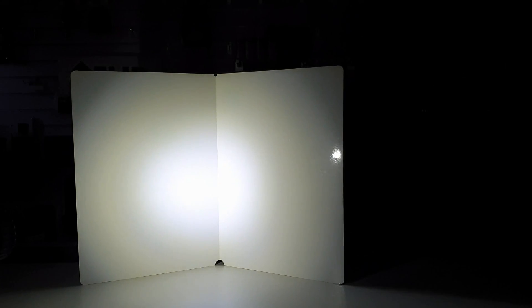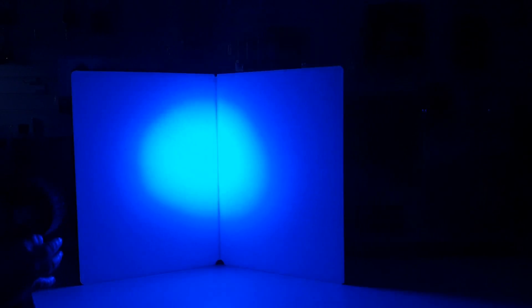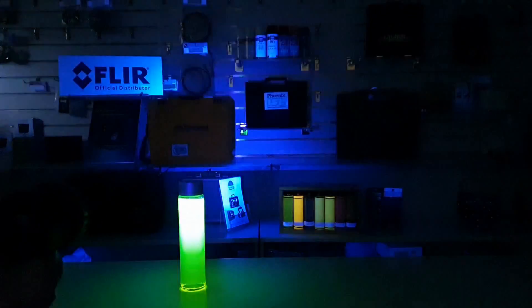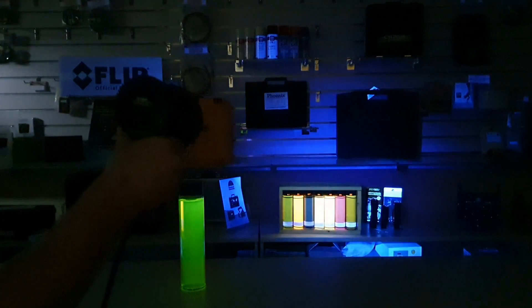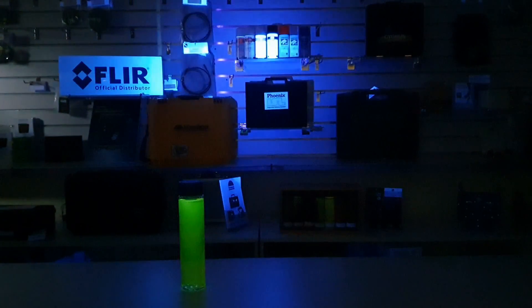I've dimmed the lights in the room to make this a bit easier to see on the video. We're going to have a quick look at the output of the lamp. So here I have the white light — as you can see it's more than enough to cover the whole board, coming from the single LED in the middle. I've swapped to UV — similar size coverage, coming out of the three LEDs now. It's more than enough to cover this whole board and to illuminate this entire sample of water glow. Now if I take the board away, you'll also see it's definitely enough to light up the wall in the background, including the oil glow samples. This is the standard version, putting out about 7,000 microwatts per centimeter squared. Of course that will vary for the ASTM and Rolls-Royce compliant versions.